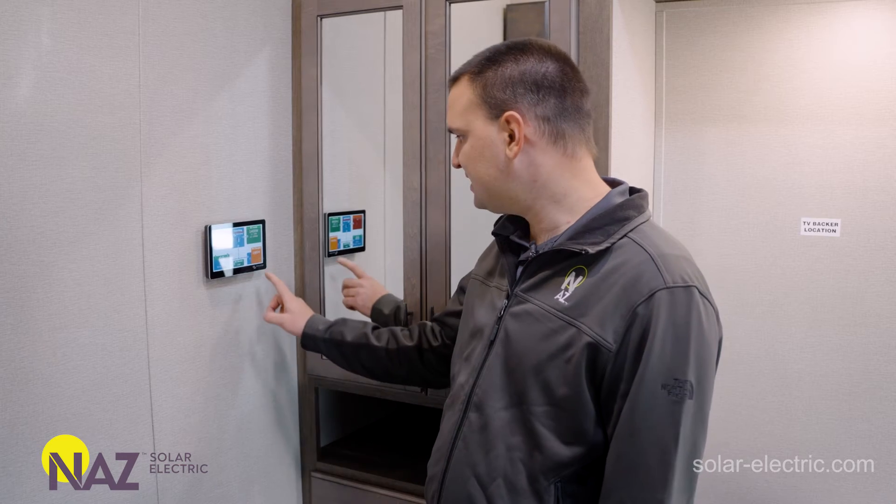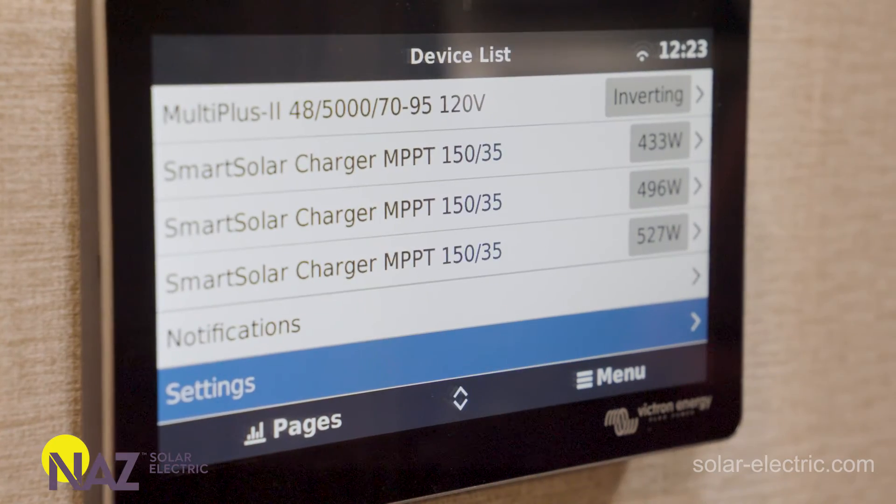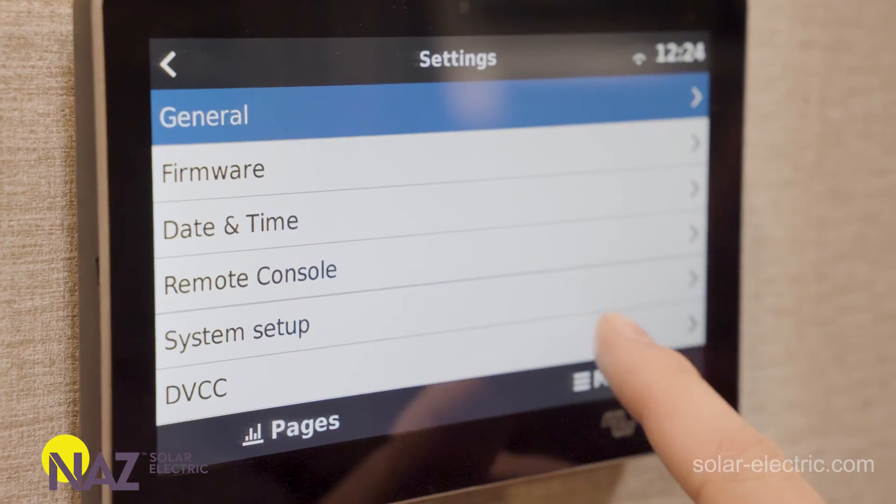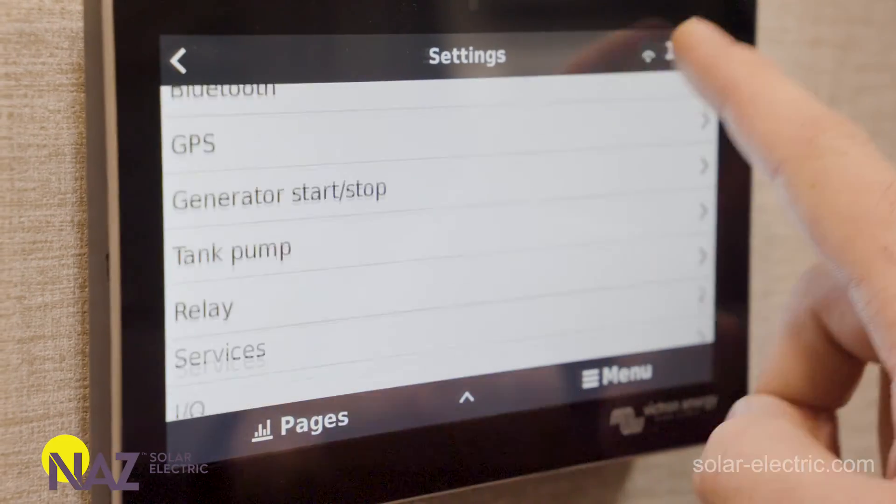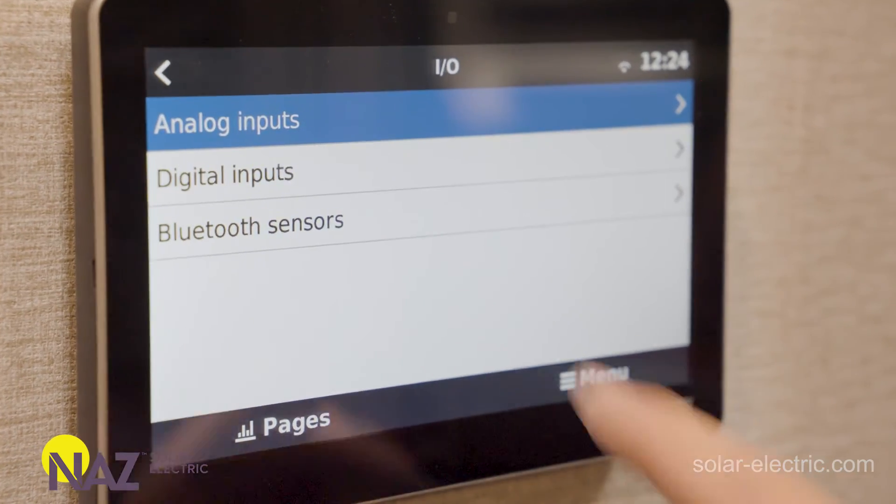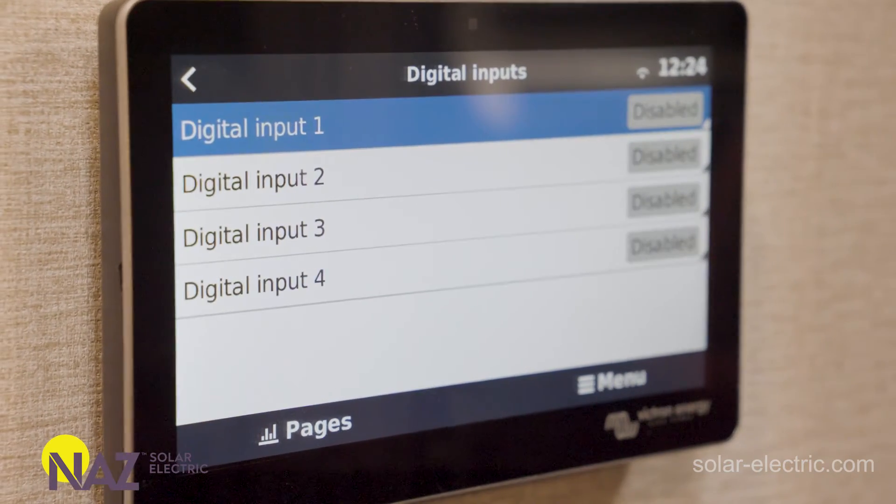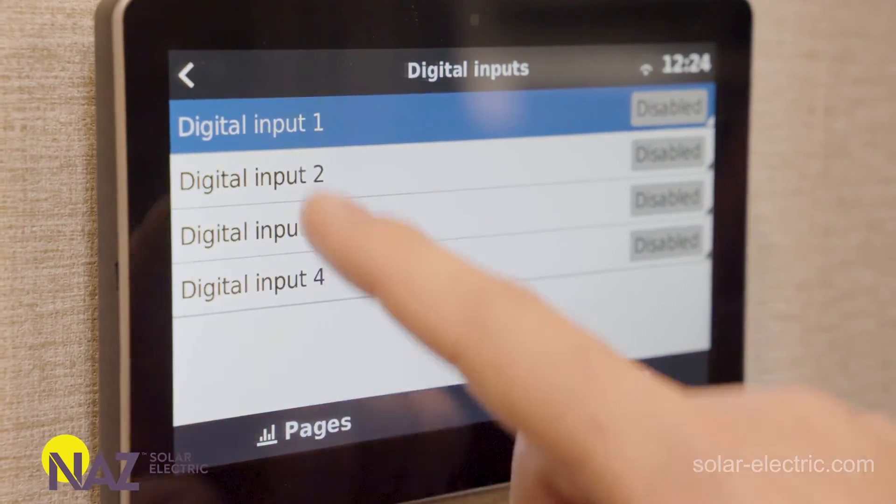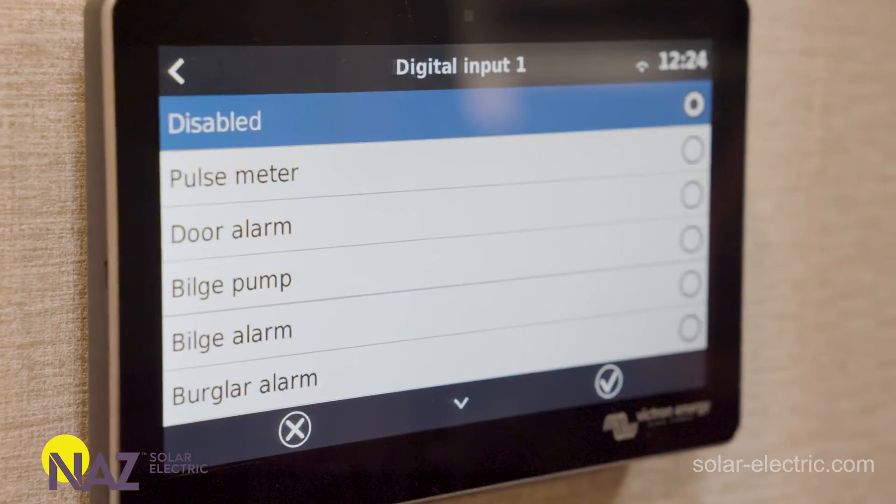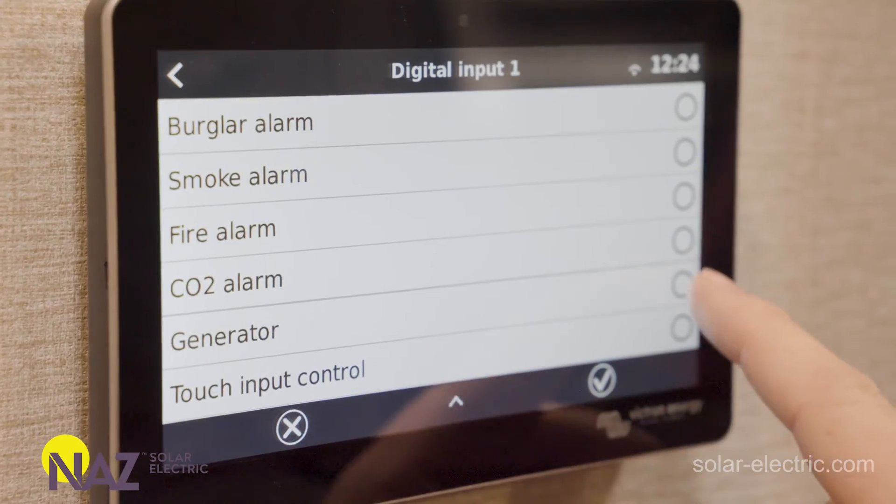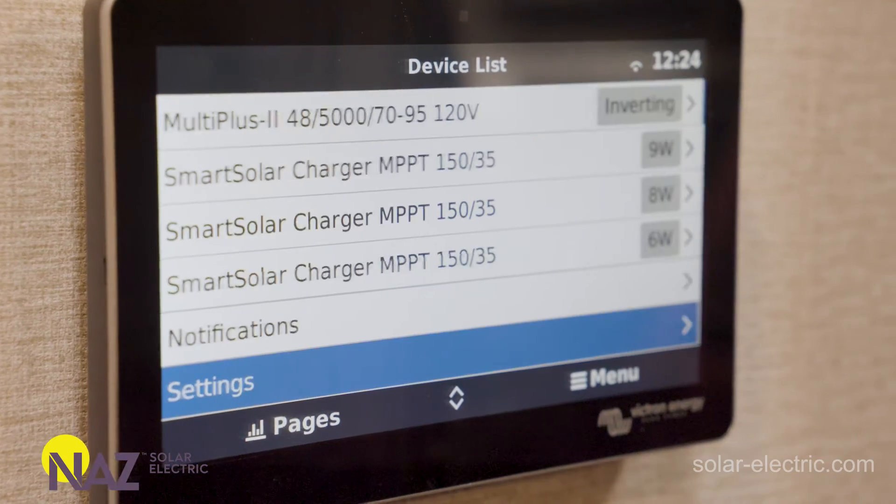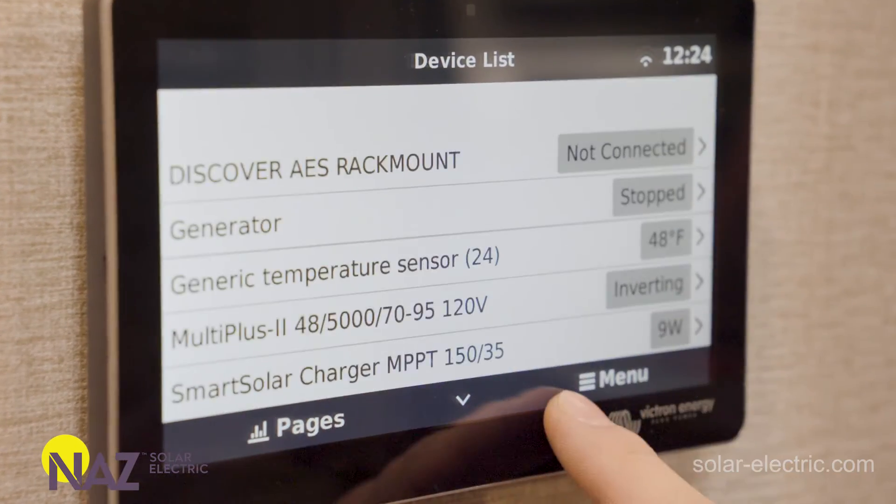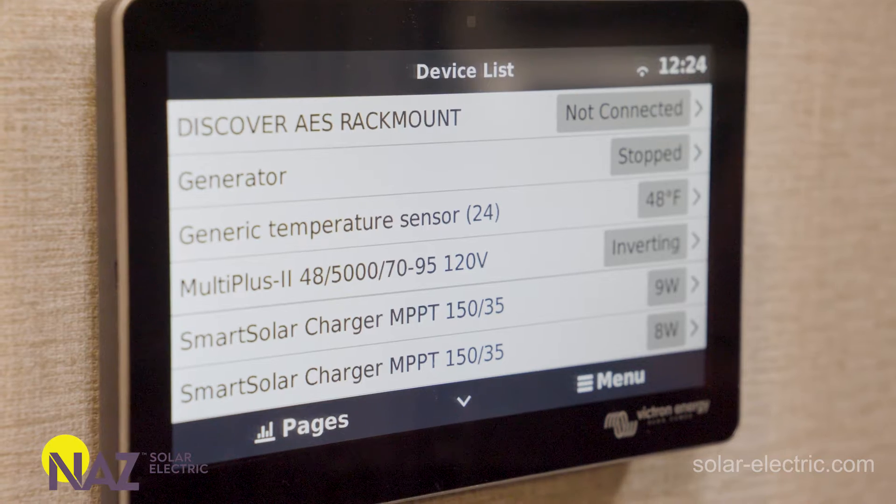We're going to go to settings. We're going to scroll all the way down to digital inputs and outputs, short for IO. We're going to go to digital inputs. The automatic transfer digital output was wired to digital input 1. We're going to go there. We're going to find the generator and we're going to select it. Now the system knows when the generator is stopped or running.